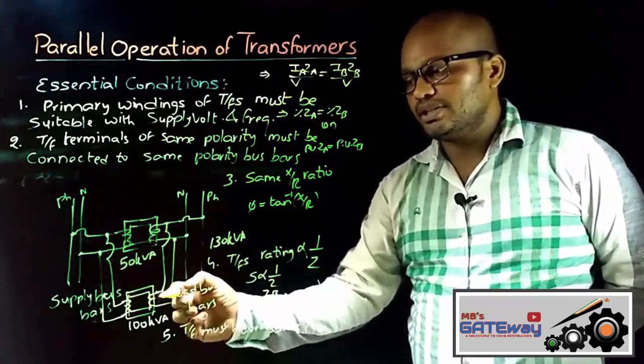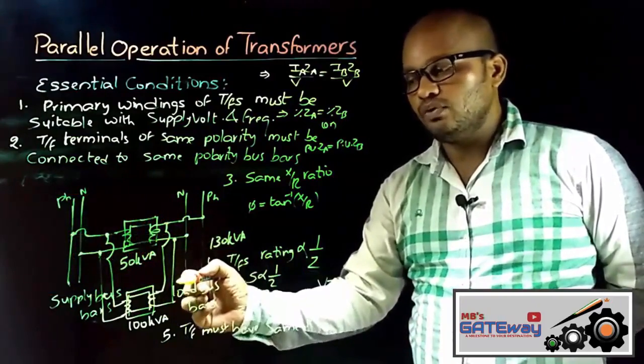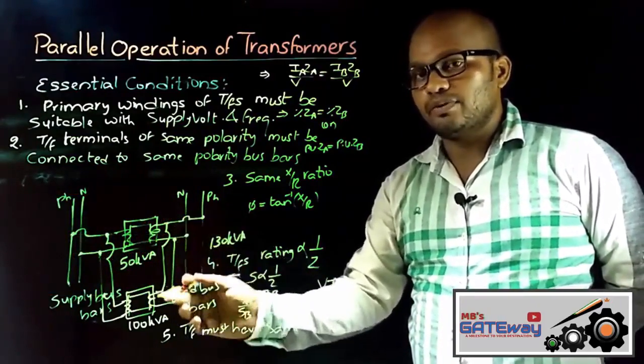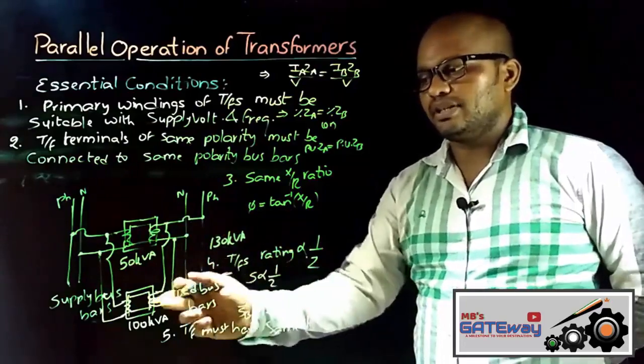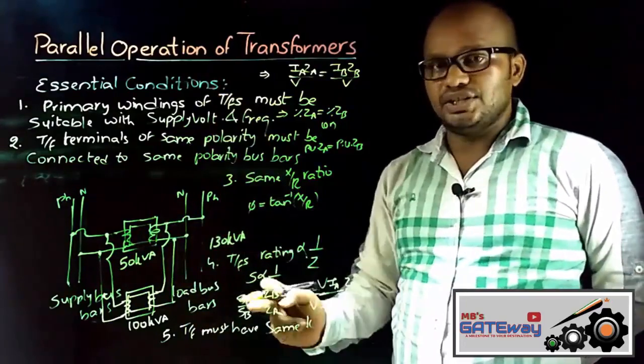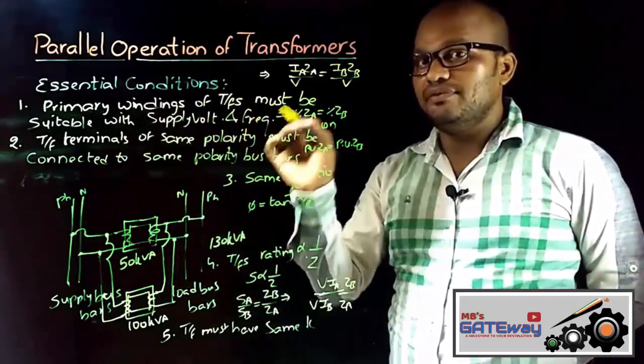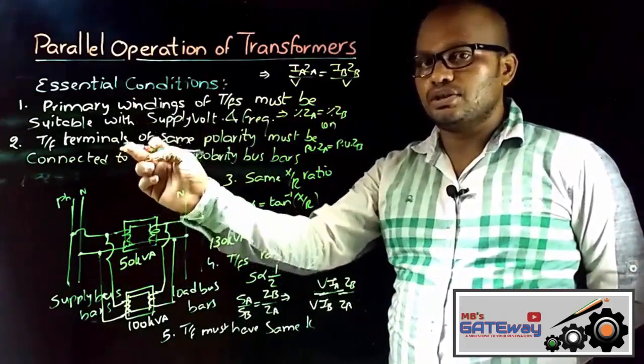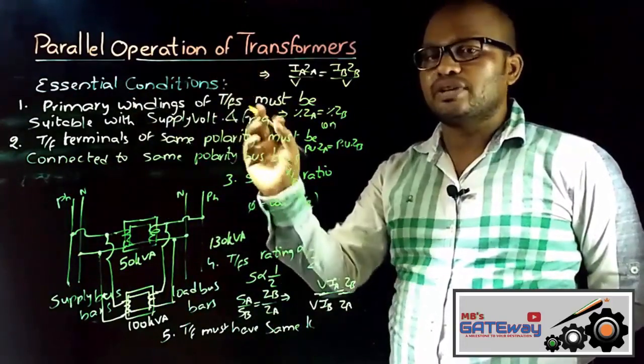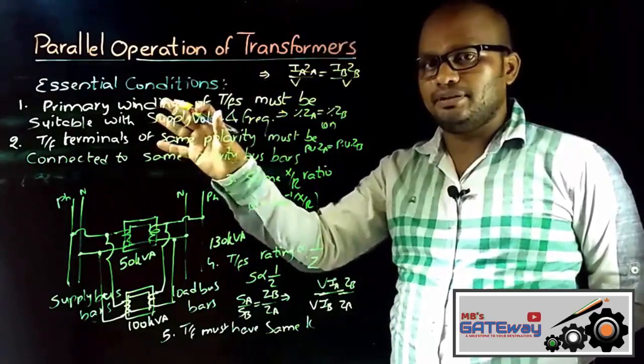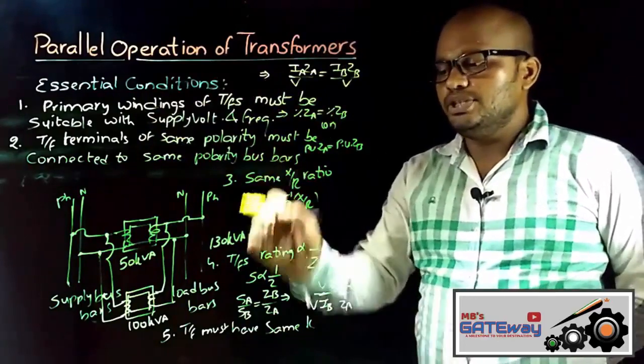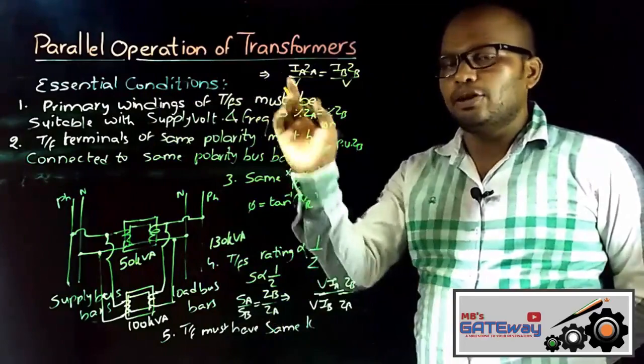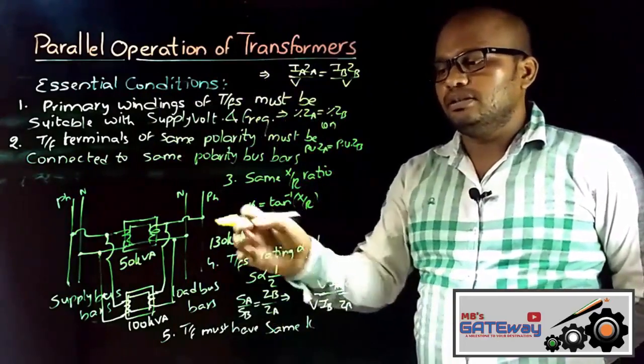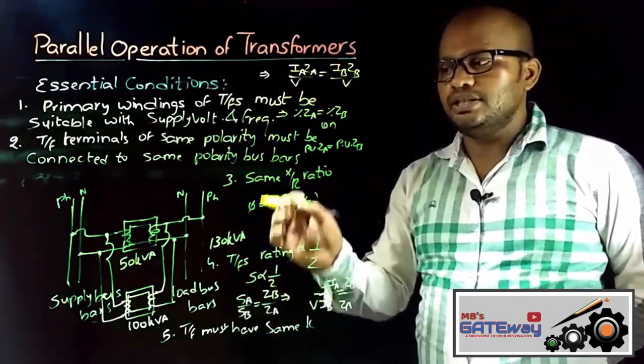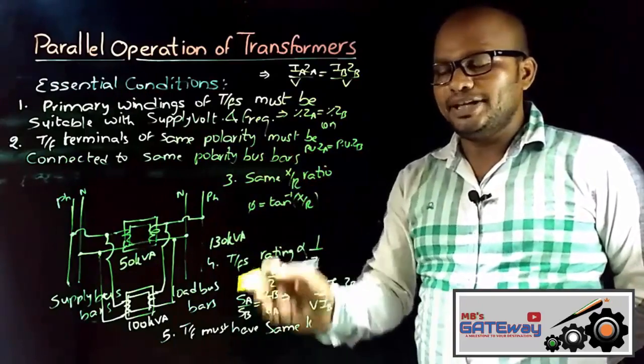If the transformer induced EMFs are not the same, then in this circuit a circulating current IC will flow, because of which the transformers will share the load unequally. Of these conditions, the first two are very essential. If these two conditions are not met, then parallel operation of transformers will not happen. Whereas even if the other three conditions are not met, parallel operation is still possible, but there will be unequal load sharing. That is, there will be inappropriate load sharing.